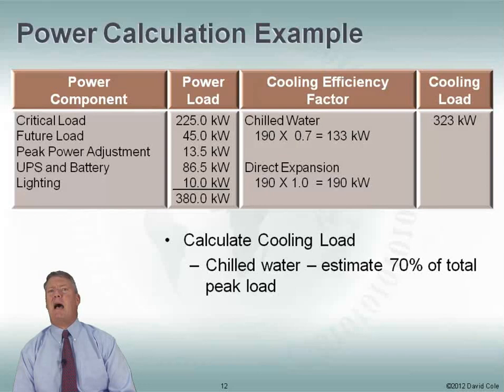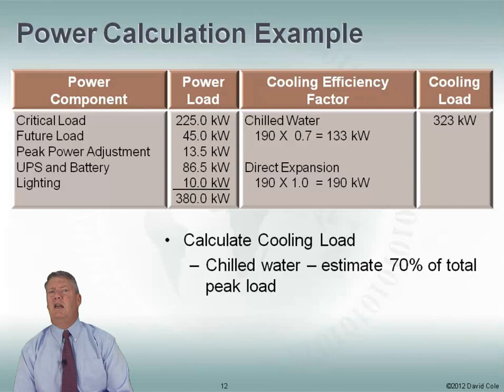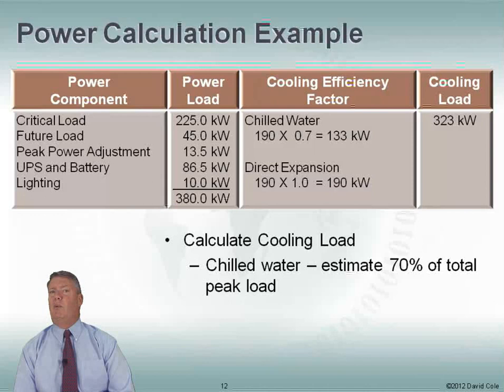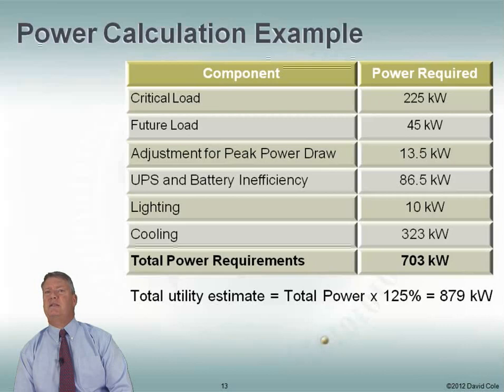Now I need to add in cooling. Half of my cooling will be done with chilled water — cooling 190 kilowatts. Chilled water is pretty efficient, drawing about 0.7 times that load, so 0.7 times 190 gives 133 kilowatts. Direct expansion is not quite as efficient — to cool 190 kilowatts it takes another 190 kilowatts. Adding those together gives a cooling load of 323 kilowatts. Adding that to our 380 kilowatts, we're now at 703 kilowatts — these are conservative numbers, but I don't want to get caught without space, power, and cooling.